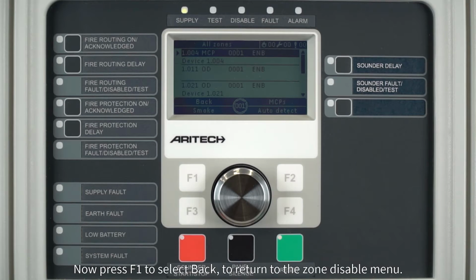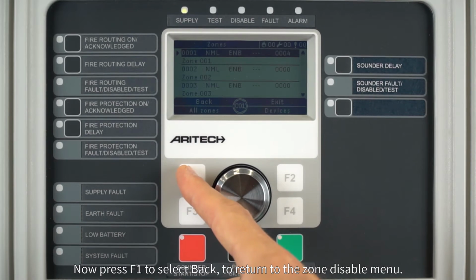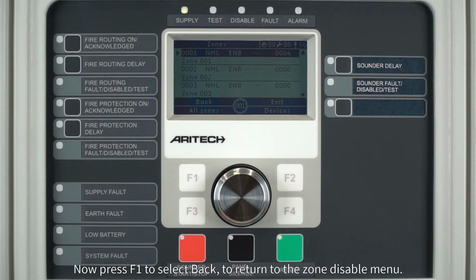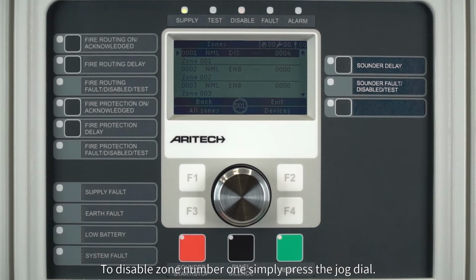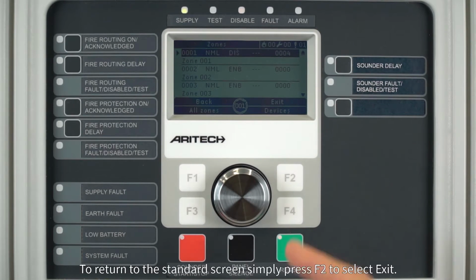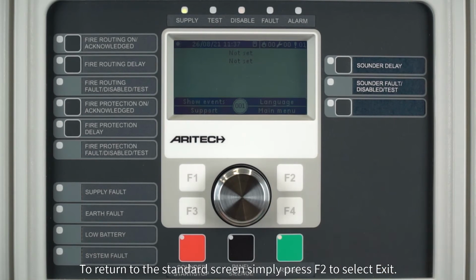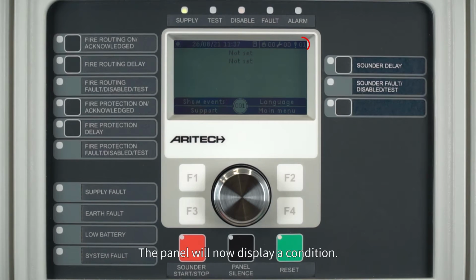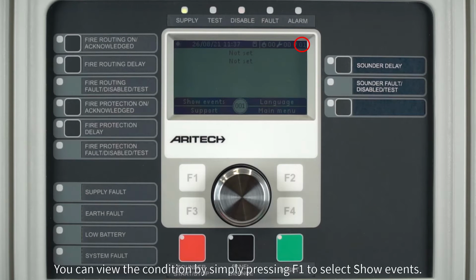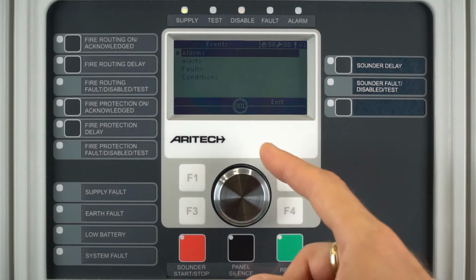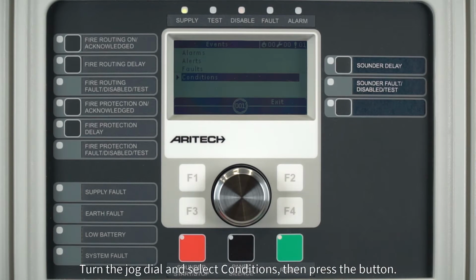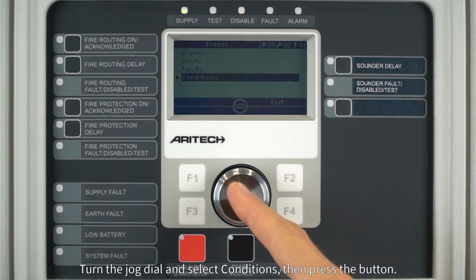Now press F1 to select back, to return to the Zone Disable menu. To disable zone number 1, simply press the jog dial. To return to the standard screen, simply press F2 to select Exit. The panel will now display a condition. You can view the condition by simply pressing F1 to select Show Events. Turn the jog dial and select Conditions, then press the button.